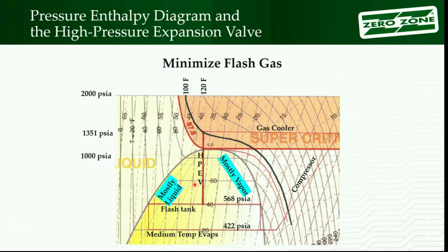When I come down, I'm going to connect vertically down, because it's only a pressure change, and I'm going to hit my flash tank. If I raise my pressure, up to the left, software says I want to go up, I'm going to pay a penalty: more electricity is being used, a little less efficiency in the compressor, but I'm going to wind up getting more liquid. I get less flash gas, I get more liquid, possibly better efficiency, possibly more capacity. If I go the other direction and lower that pressure, I'm dropping in down here, and I didn't necessarily have to lower the pressure a whole lot. I'm getting a lot of flash gas, not a lot of liquid, losing capacity and efficiency in the system.